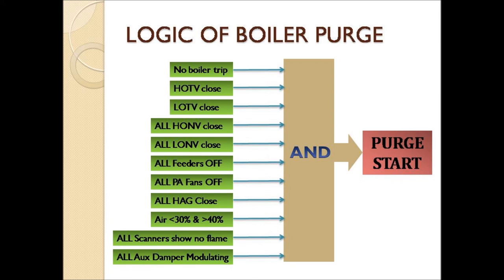This is the complete logic of boiler purging. Through this logic we can clearly understand the conditions and permissives of boiler purging. All these conditions are routed through an AND gate, meaning all of these conditions are required to go for boiler purging. If any one of these conditions does not meet, then we cannot go for purge start. Once all conditions are true, we can go for purge start and a 5-minute purging cycle will begin. During this 5-minute cycle, if any condition goes false, the purging will halt. In technical terms, if purge halts midway, it is called a purge interrupt.